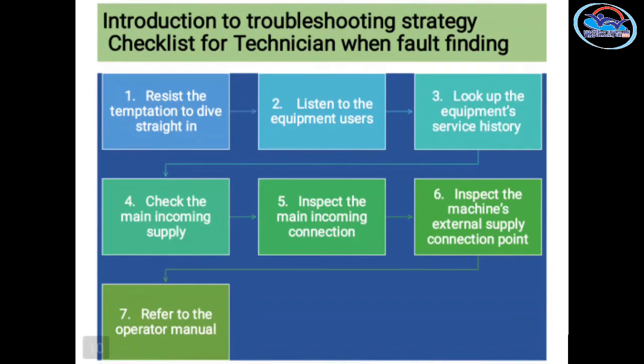Do not immediately open up the machine and bang it with a screwdriver — that is not the right approach. First, listen to the equipment users in whatever department or section they are in. Second, look up the equipment service history. In the Biomedical Engineering Department, the equipment service report and service history should be reviewed.